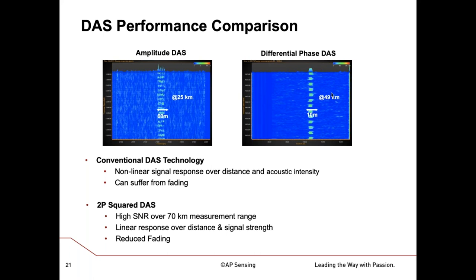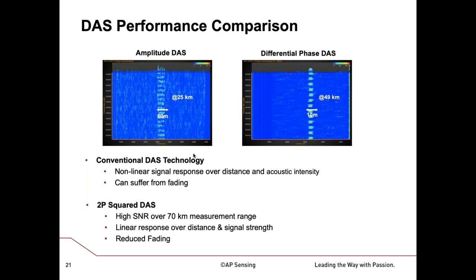Here's another example: on the left, AP Sensing's early DAS at 25 kilometres, showing a signal that's not uniform in intensity along it, which it should be. The plot on the right is from a differential phase DAS, doing phase differencing along the length, and you can see the signal is a uniform strength. Also, we're now doing this at 49 kilometres rather than 25. So although we call them both DAS, they're definitely not the same in terms of signal quality and what you can do with the signal afterwards.